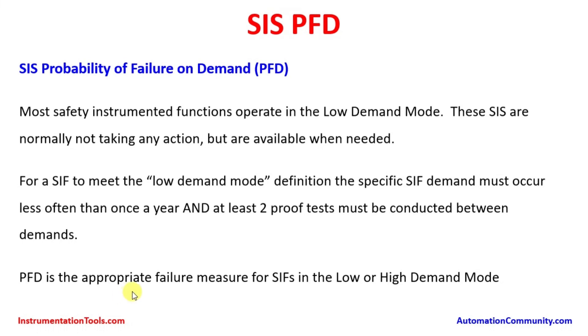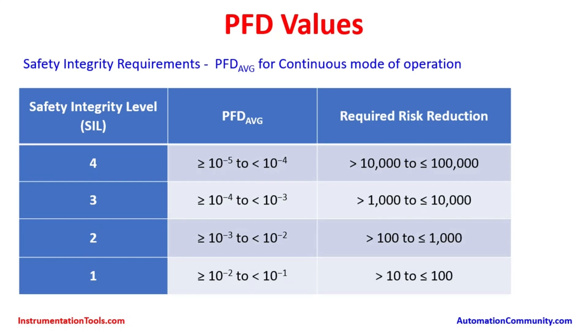PFD is the appropriate failure measure for safety instrumented functions in the low or high demand mode. Now we will go over the values of PFD. Safety integrity requirements — PFD average for continuous mode of operation. These are the different safety integrity levels from 1 to 4. With Safety Integrity Level SIL 1, the PFD average should be more than 0.01 and up to 0.1, that is 10 to the power minus 2 to 10 to the power minus 1. The required risk reduction, which is the inverse of the PFD average, should be more than 10 and less than 100.